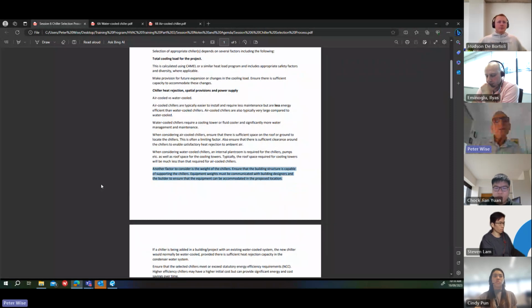If a chiller is being added to an existing building or project with an existing water-cooled system, the new chiller would obviously normally be water-cooled. You add that onto the system, provided you've got enough heat rejection capacity in the condenser water system. If you don't, then you might need more cooling towers, more fluid coolers to accommodate the extra chiller. And then the spatial requirements comes in again.